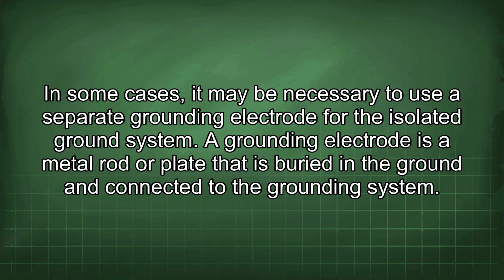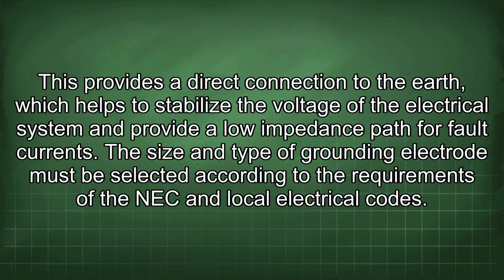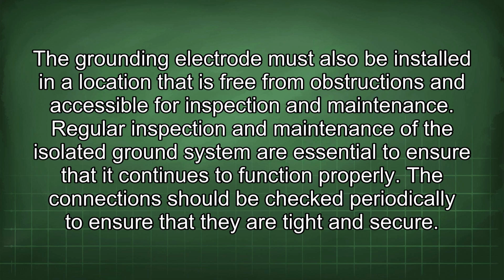A grounding electrode is a metal rod or plate that is buried in the ground and connected to the grounding system. This provides a direct connection to the earth, which helps to stabilize the voltage of the electrical system and provide a low impedance path for fault currents. The size and type of grounding electrode must be selected according to the requirements of the NEC and local electrical codes. The grounding electrode must also be installed in a location that is free from obstructions and accessible for inspection and maintenance.